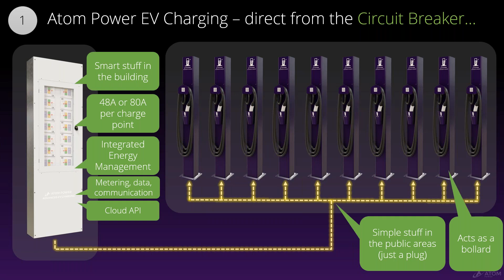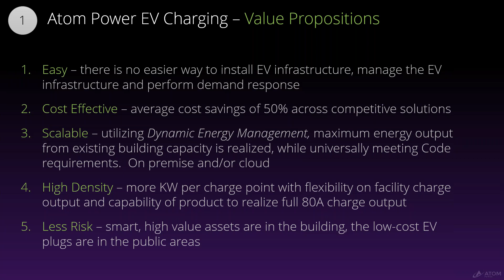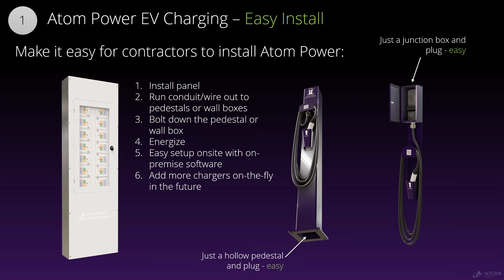So our value proposition here for the EV charging: there's no easier way to install EV infrastructure or manage that infrastructure than using our Atom Power solution. It's cost effective, it's very scalable. Not only is the energy management within the panel, there's dynamic energy management, which allows you to connect to an IP meter of your building. So you can manage your energy of the whole building. I'll talk about that here in a minute. Also, high density, you get the full 80 amps of output if that's what you want, and less risk due to your smart high value assets being in the building as opposed to exposed to damage by a vehicle. It's easy to install. You can install a panel, you can run conduit and wire and land the wire on a terminal block. That's all you need to do to install our panels.